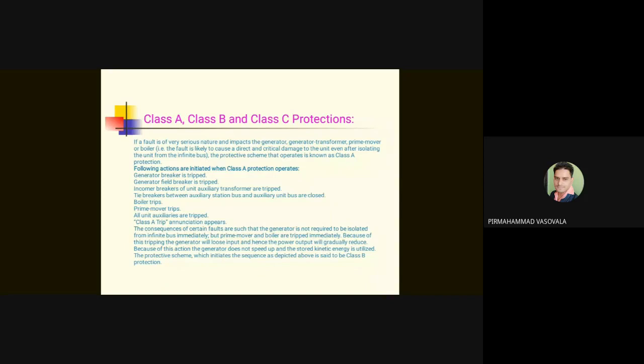Class B is a little different from class A. A class B type of situation will come only if the fault is not very severe, particularly if the fault is outside the generator, and therefore complete tripping immediately is not desired. Therefore, what is done is we make use of the kinetic energy of the generator in this case, because when you trip class A, the complete load is lost. Therefore, there are chances of the generator accelerating. There are chances of overspeeding of the generator.